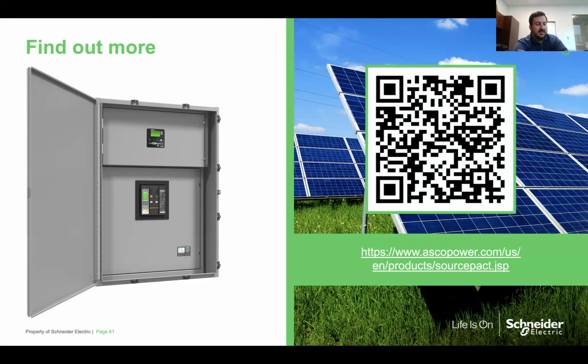So UL 3008, like any UL standard, really has a focus on two pieces: the performance electrically of the equipment itself, and there's all sorts of testing that goes into it, like endurance, meaning the number of cycles and operations it can do. How can it handle a short circuit, to make sure that if there is a fault downstream, our equipment further upstream isn't going to be the point of failure in the system? The endurance testing makes sure you're not going to operate it twice and have it break down. It can operate several thousand times for the expected life of the equipment, and it's going to hold up.